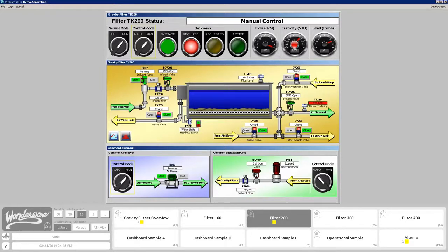Other things that can often happen can be things that are, say, distracting. So what I'm going to do is open the air blower, open the air inlet valve here, and I'm going to show how in this particular demo there were a lot of these bubbles. These things are indicating bubbles, which are trying to indicate that there is air going through this system. At this point now, is that a problem? Is this expecting the operator to act?